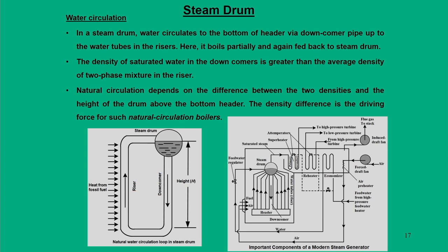We will talk about specific components: in the steam drum we have risers and downcomers. The downcomer is for water to come out from the steam drum, and the riser is for steam that goes up into the steam drum. The water comes down through the downcomer at height h, receives heat from the fossil fuel, and rises again into the steam drum. This process is called natural circulation.